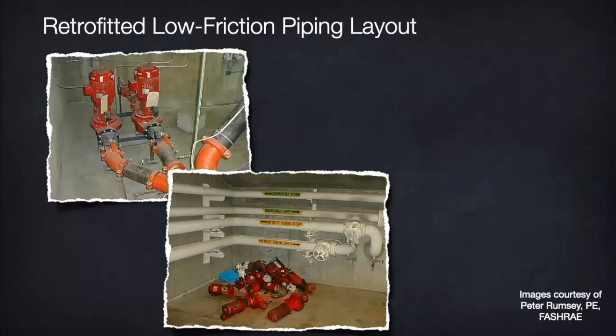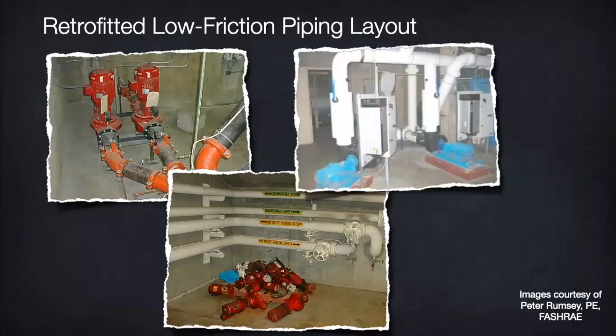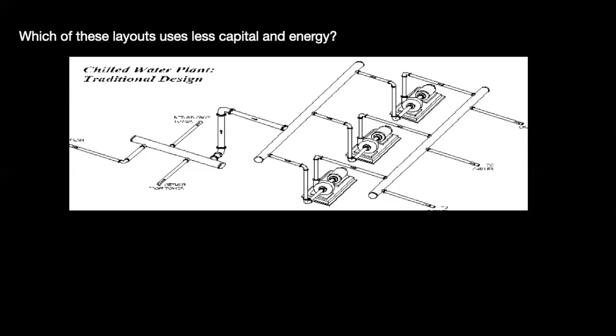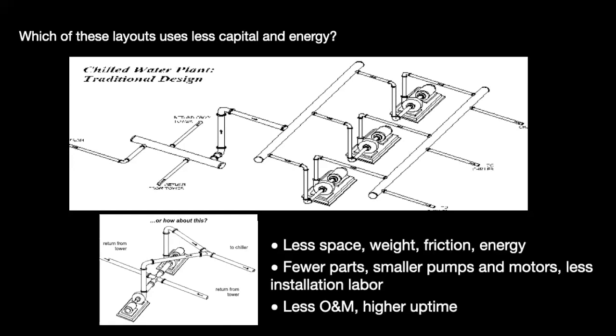Repiping another pumping loop and adding variable frequency drive doubled the flow and saved 85% of the energy. Peter just asked the pipe fitters to lay out the supply pipes as if they were drains. Here's how most big buildings pipe cooling tower water back to the condenser. But if we lay it out instead as Peter does, everything gets better. The only obstacle is force of habit. We should bend minds, not pipes.